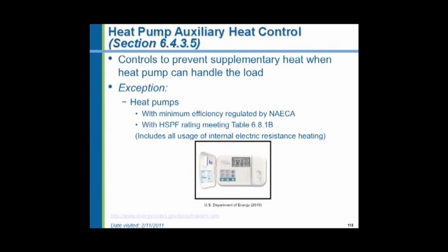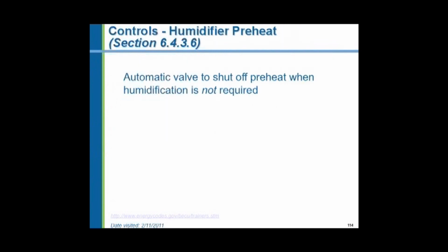Heat pumps have to be sized exactly. They don't want to oversize the heat pumps, and they are allowed to have some supplemental heating. And it can be electric resistance heating. If the heat pump is not capable of heating the building to the required temperatures in the middle of the heating season, in the wintertime, we are allowed to have some supplemental electric heat. But they have to have controls.